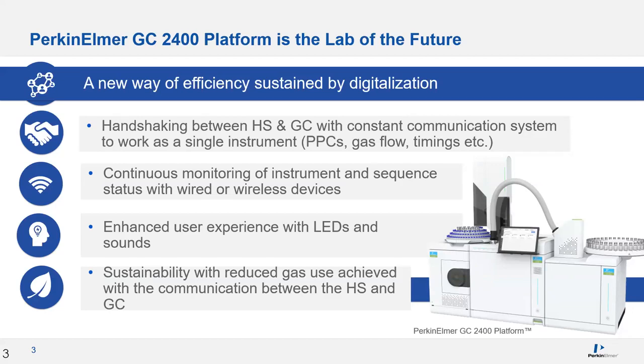This integration is also in our instruments, where now the instruments have a SOM and their own IP address — essentially an internal computer. This allows connection to our instruments with any device within your network that has the right permissions, which means you can have continuous monitoring and even get notifications.